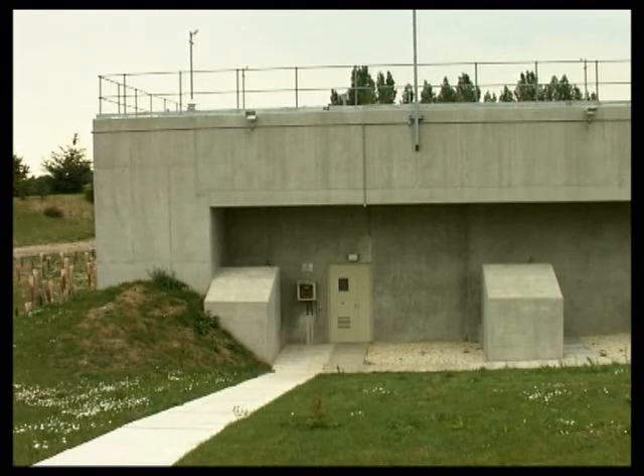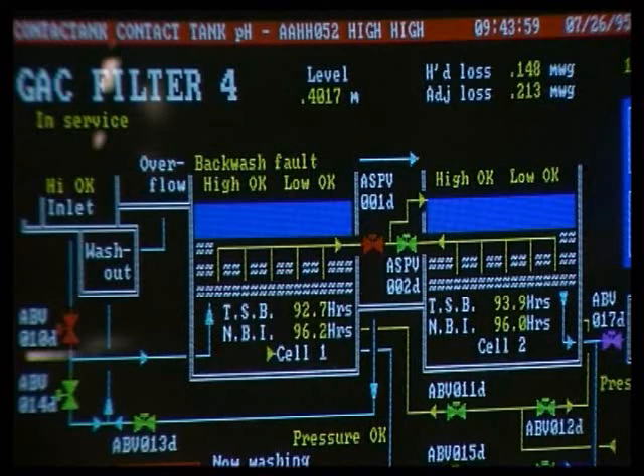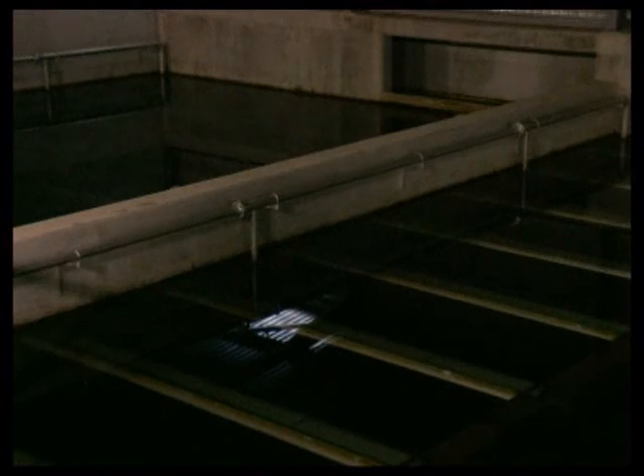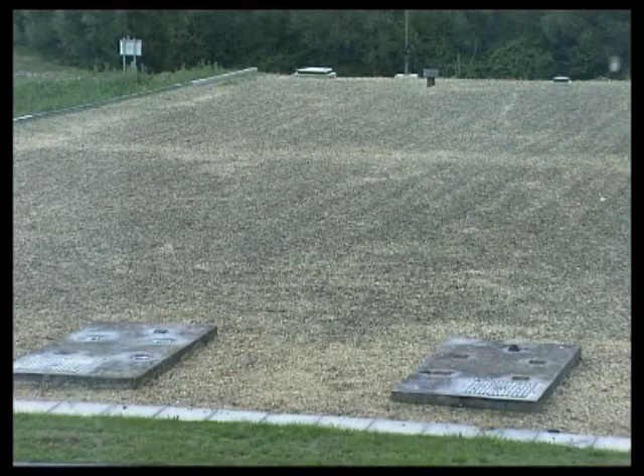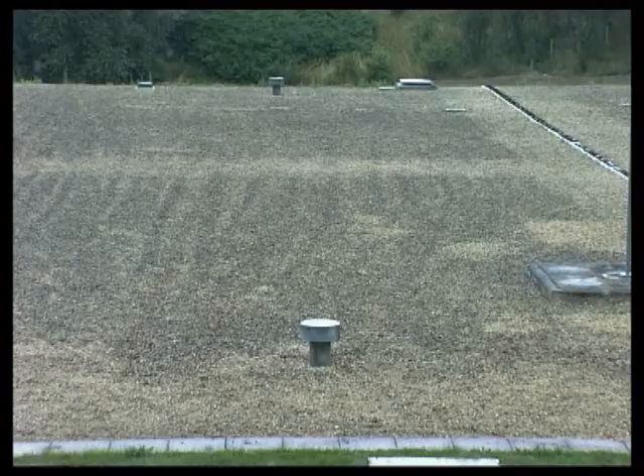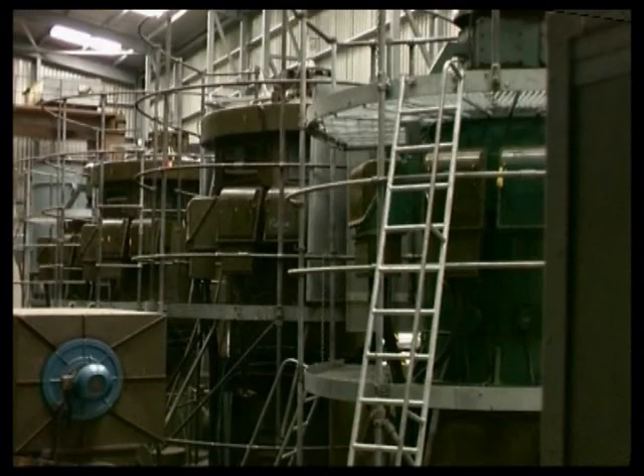The filtered water travels to the next stage, where it's treated with ozone for a second time. After ozone treatment, the water is fed through activated carbon adsorbers, which remove any remaining organic matter. In the final stage, chlorine is added. Only a tiny amount is needed to maintain water purity as it's pumped to local service reservoirs and onto the local distribution system.